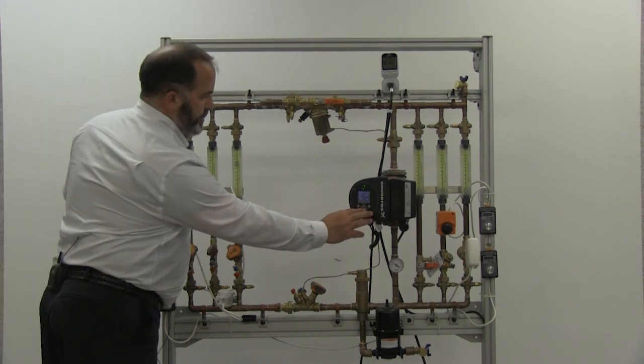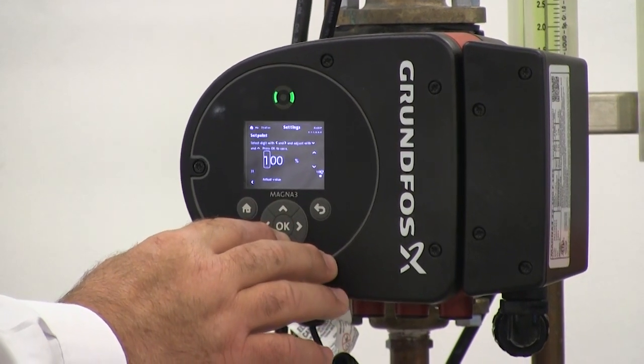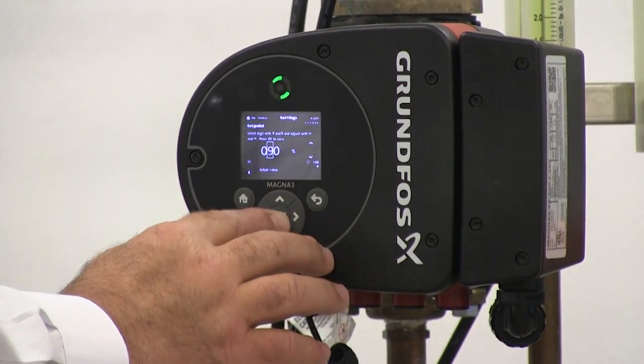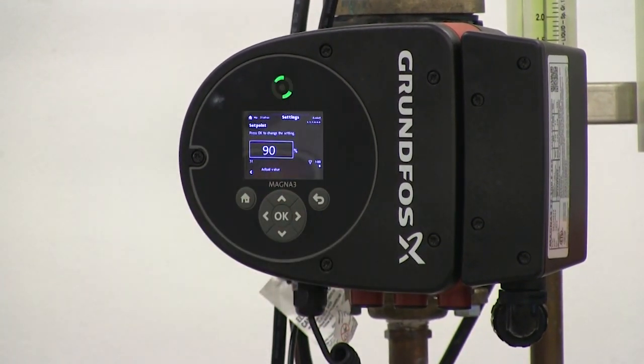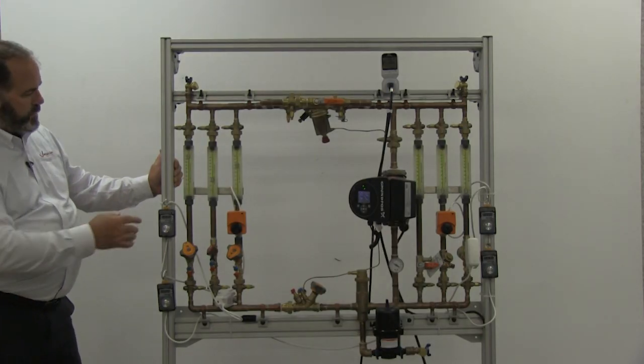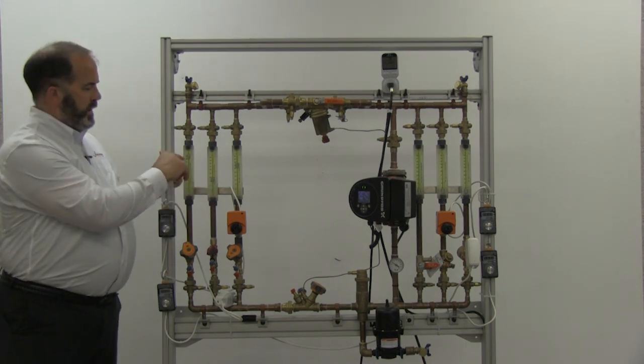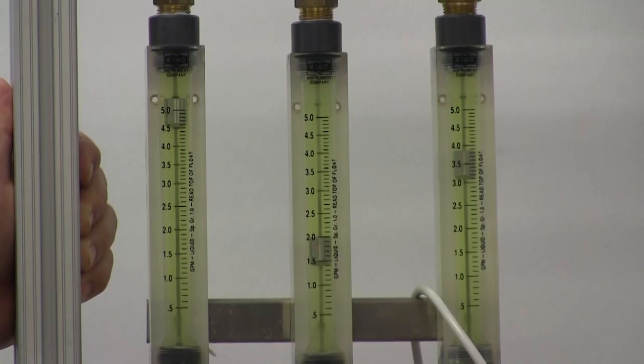So in this case I'm going to ramp my pump down. And about 90% should about get us there. So now you can see I'm at my design flow for my index coil, but I'm still overflowing on my two other coils.